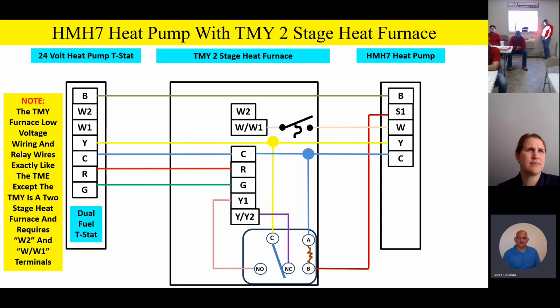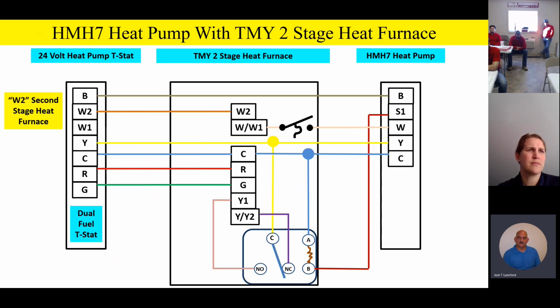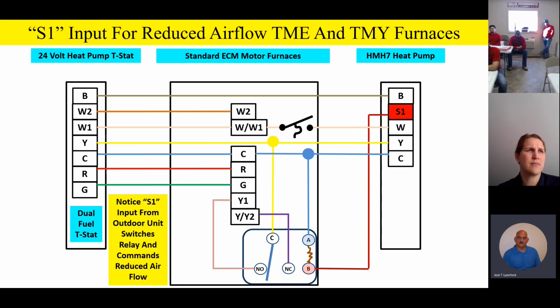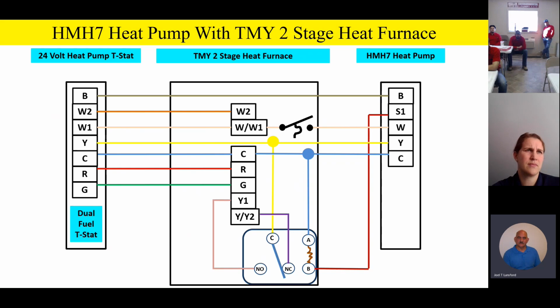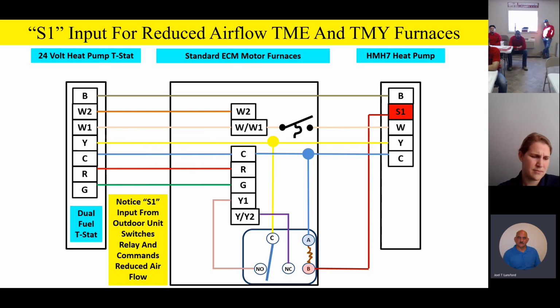All right, fellas, just remember then, on the TMY, which is a 2-stage furnace, it wires exactly the same, except there's going to be an additional terminal because it's a 2-stage heat. So basically, you'll have a W2 input for 2nd stage heat, and then your W/W1 will be for 1st stage heat. And so that's the only difference between the two furnaces as far as the low voltage wiring. In addition, when we go ahead and do the animation, you'll see that when we energize S1, just like we did before, we're going to switch that relay and command low airflow or reduced airflow when the outdoor unit says, hey, I want low airflow or reduced airflow because I'm at a point of modulation right now that will allow that airflow to be reduced.